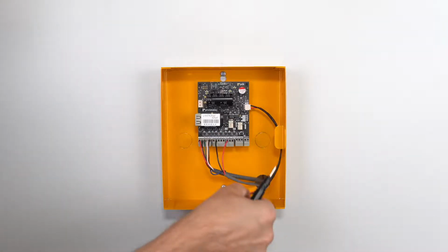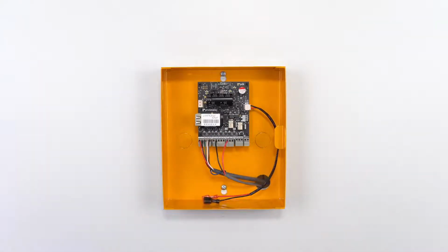Looking at the connectivity here, I've got the positive red wire into my DPS input, and the negative wire connected into a ground. On the other end, it's connected to a door position sensor. When the door is closed, the reed comes up because the magnet at the top of the door pulls it into the closed position and makes a ground loop, so the controller knows the door is closed. When the door opens, the reed pops back open and breaks that connectivity.